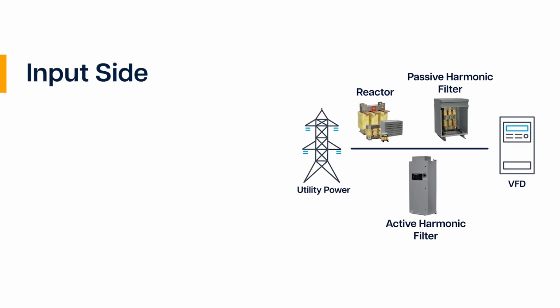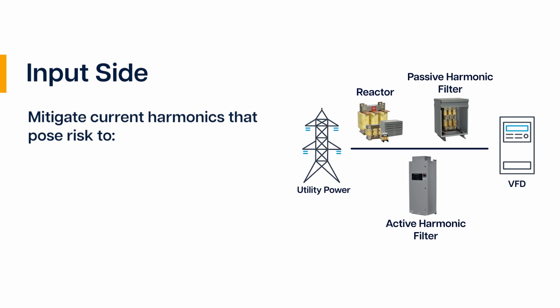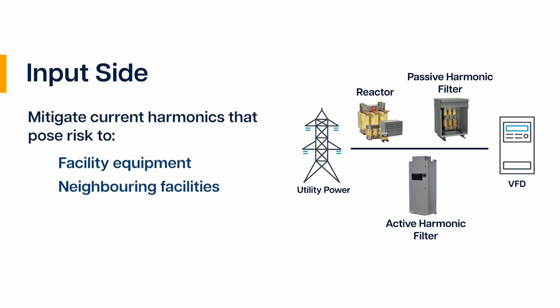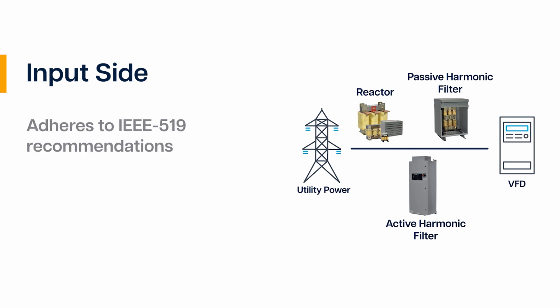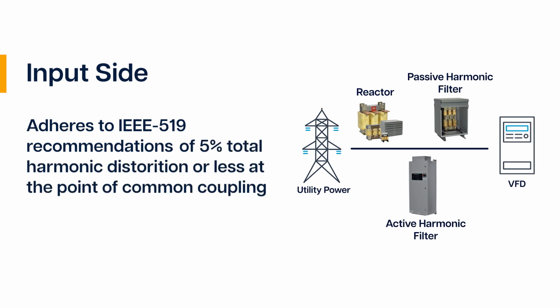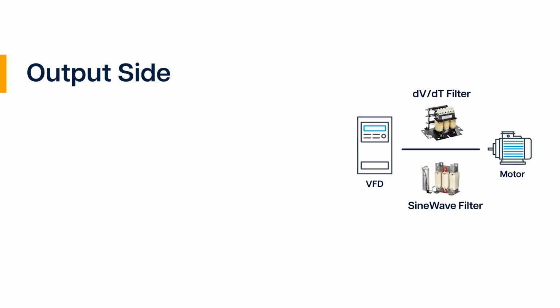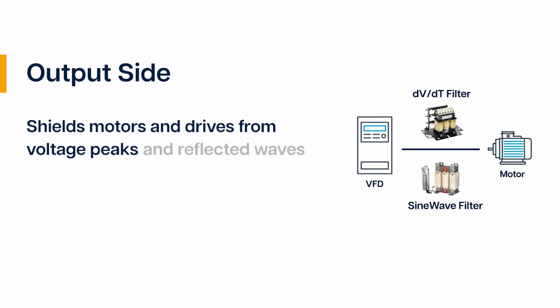On the input side, we focus on mitigating current harmonics that pose risks to facility equipment, neighboring facilities, and the utility grid, adhering to the IEEE 519 recommendation of 5% total harmonic distortion or less at the point of common coupling. The output side concentrates on shielding motors and drives from voltage peaks and reflected waves.